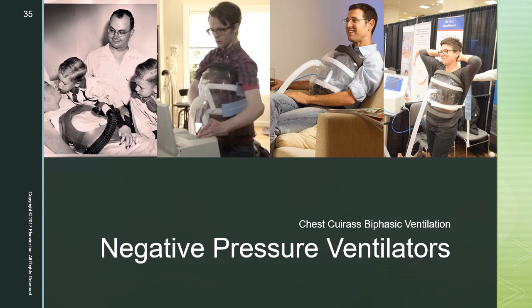The original negative pressure ventilator was the iron lung, and it was used for patients needing ventilator assistance after polio. For practical reasons, that cumbersome iron lung was essentially replaced by the chest cuirass, wrap, or pneumosuit. The chest cuirass, a rigid shell that's pictured here, and the wrap-type system, nylon fabric surrounding a semicircular tent-like support, are simply enclosures that allow the application of negative pressure to the chest. These devices require a separate electrically powered negative pressure generator. An example of a negative pressure generator used to power cuirass or wrap type systems is the Respironics NEV100.